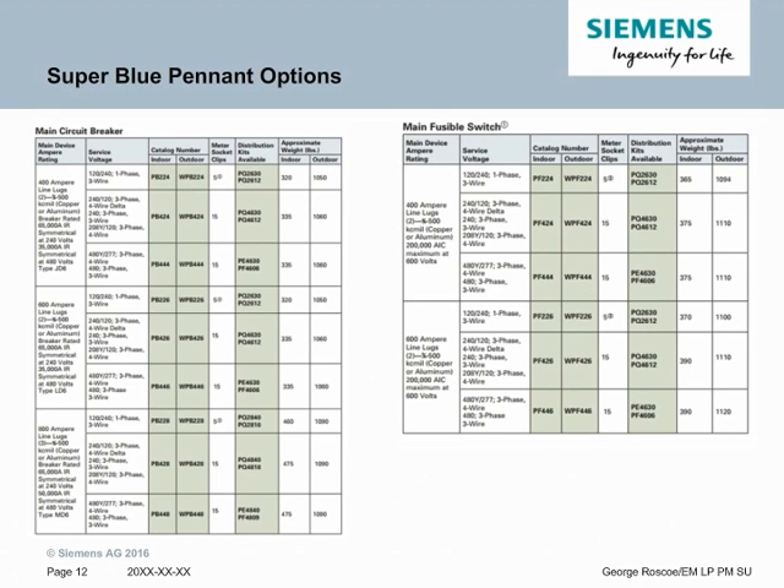Here are the major options for a Super Blue Pennant. Each Super Blue Pennant size and ampacity has an indoor and outdoor version. There are three core ampacities for the main circuit breaker and two for the main fuse. Additionally, there are different voltages available including single phase, three phase 208 four wire, and three phase 480 four wire. They also come in options with the main breaker and the main fuse switch. Also on the right you'll see distribution kits available — these are the size distribution kits you can put in at the bottom of a Super Blue Pennant.